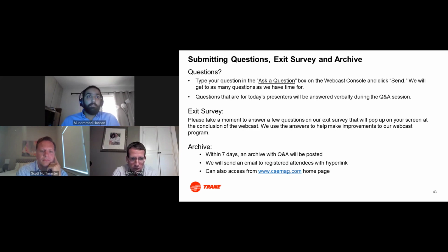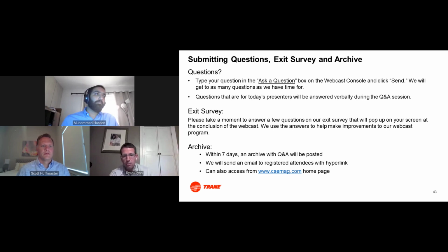and you're getting the correct capacity. Because you could have a situation where your mixed air temperature exceeds 80 degrees or is well below 80 degrees, and your nominal 2-ton unit is operating like 1.5 tons, and that could affect your loads and the temperature in the space. So I guess short answer, it depends, but we've seen it both and we've done it both ways. Thanks, Ryan. Yes, it depends is definitely an answer.